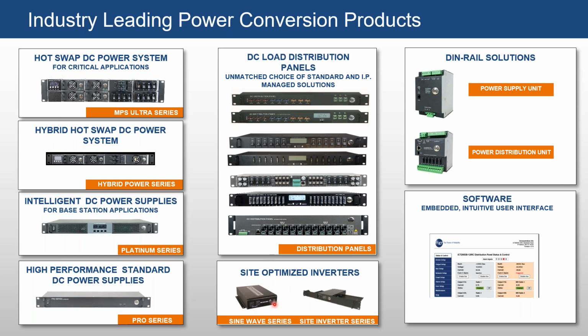We know a site cannot be completely DC, it's not possible at some places, so we have two flavors of inverters. A 300 watt basic inverter connects to the battery and provides reliable AC. The second is a 1500 watt inverter that comes with remote monitoring and control, and has dual input, AC and DC. When AC is present, it bypasses the whole thing and gives you the AC mains. When AC power is lost, it transitions to battery backup within half a cycle, so your devices don't restart or get a break.